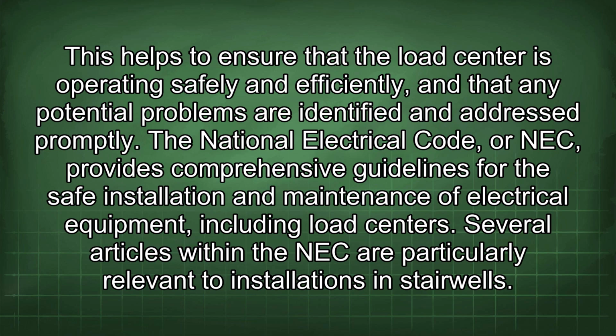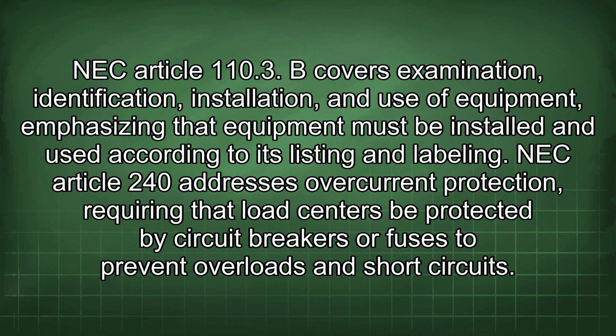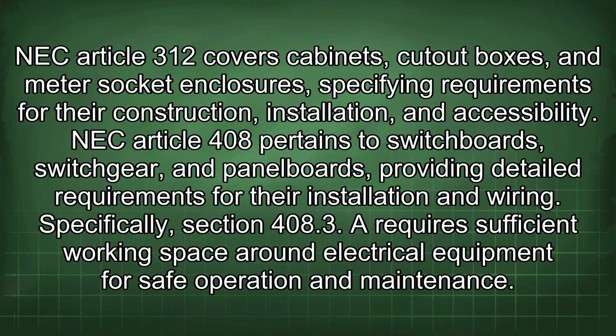The National Electrical Code, or NEC, provides comprehensive guidelines for the safe installation and maintenance of electrical equipment, including load centers. Several articles within the NEC are particularly relevant to installations in stairwells. NEC 110.3(B) covers examination, identification, installation, and use of equipment, emphasizing that equipment must be installed and used according to its listing and labeling. NEC Article 240 addresses overcurrent protection, requiring that load centers be protected by circuit breakers or fuses to prevent overloads and short circuits. NEC Article 312 covers cabinets, cutout boxes, and meter socket enclosures, specifying requirements for their construction, installation, and accessibility.